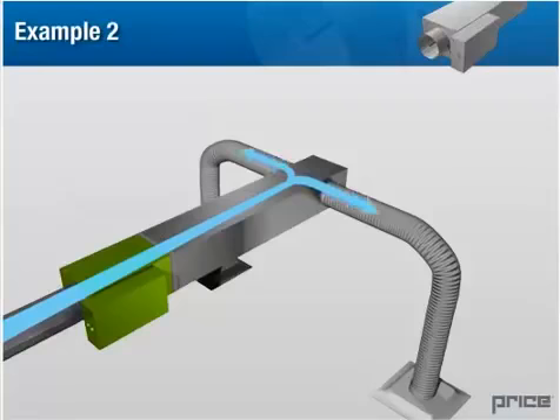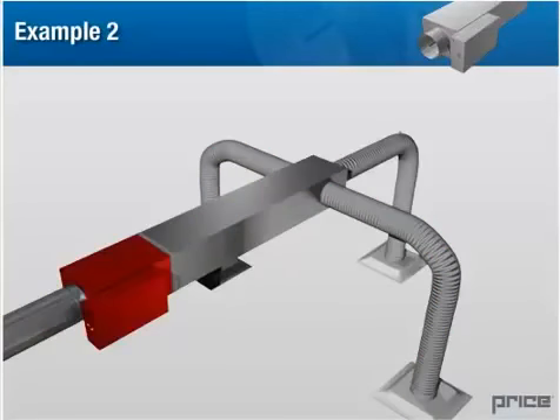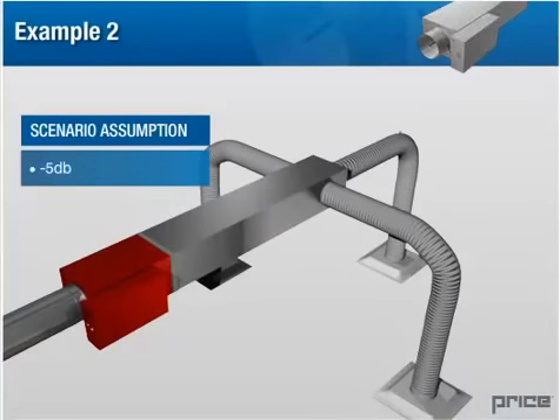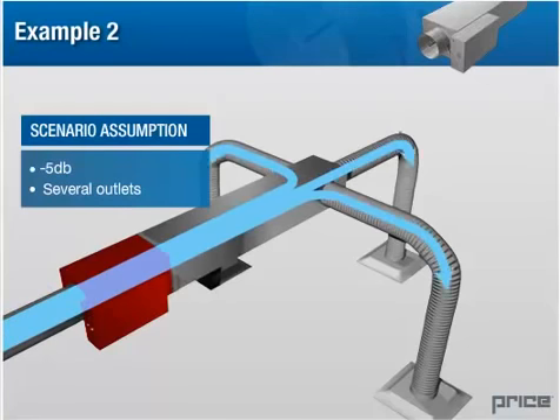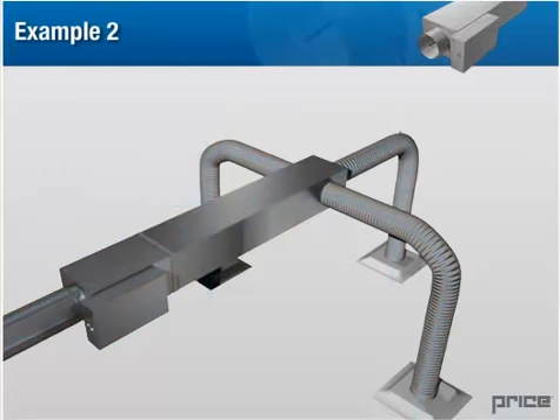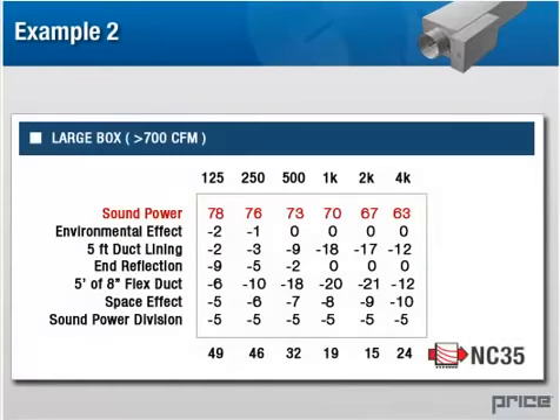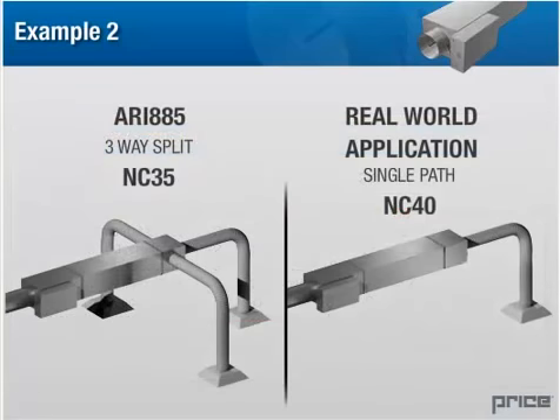This means that half of the sound energy is going down one duct and the other half is traveling down the other. Furthermore, if we look at the large box, ARI 885 allows for 5 decibels of sound power division. This would lead us to believe that the standard expects that this terminal unit has enough air flowing through it to provide air to several outlets. If we take this into account on our example system, assuming that our terminal unit is only providing one room, look what happens to our NC level. Once again, based on the assumptions provided by ARI 885, we may get ourselves in trouble with what at first looked like a good selection.